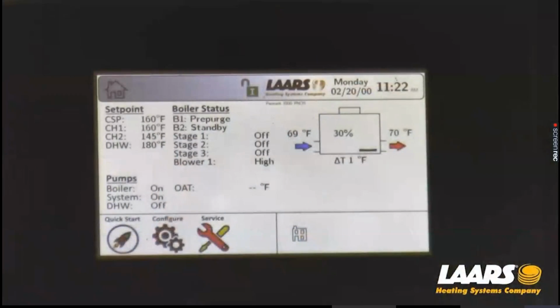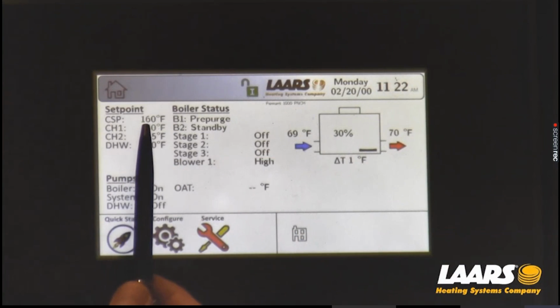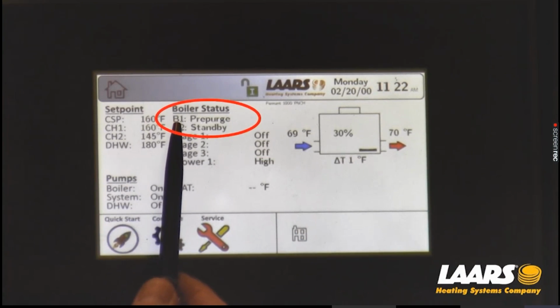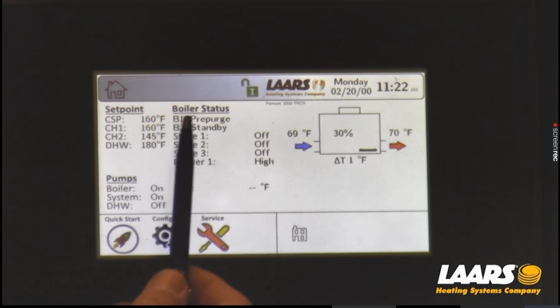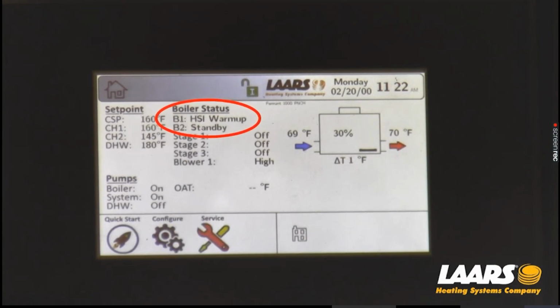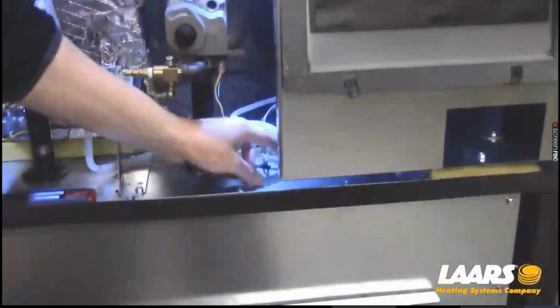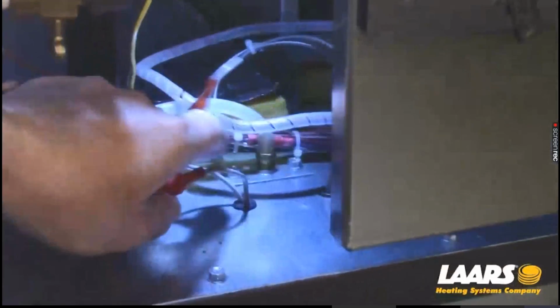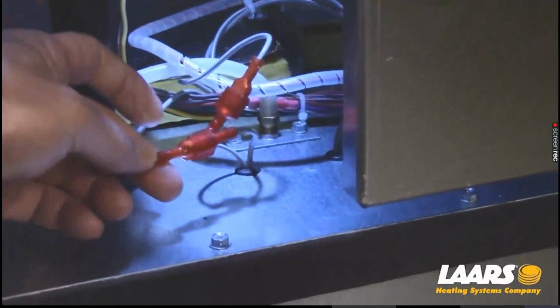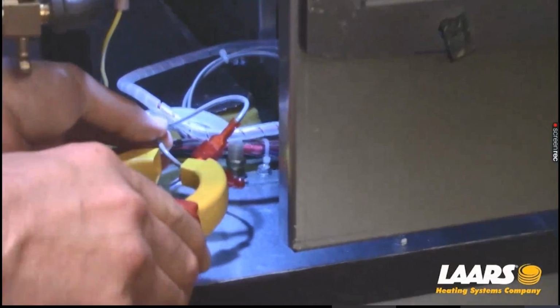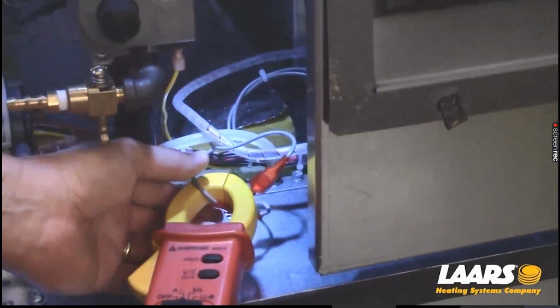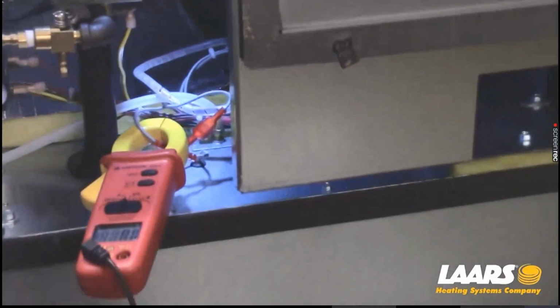Okay? So now we go back to here, and we'll see that we have a calculated set point of 160. Our blower is in pre-purge, or B1's in pre-purge, now HSI. That's the hot surface ignition warm-up period. We can take an amp probe and do a test on that. So coming down through the upper deck are the hot surface igniter wires. You may not have these Molex plugs on them. This is in our test lab. I'm going to put an amp probe on it. We're going to wait for us to go through pre-purge.